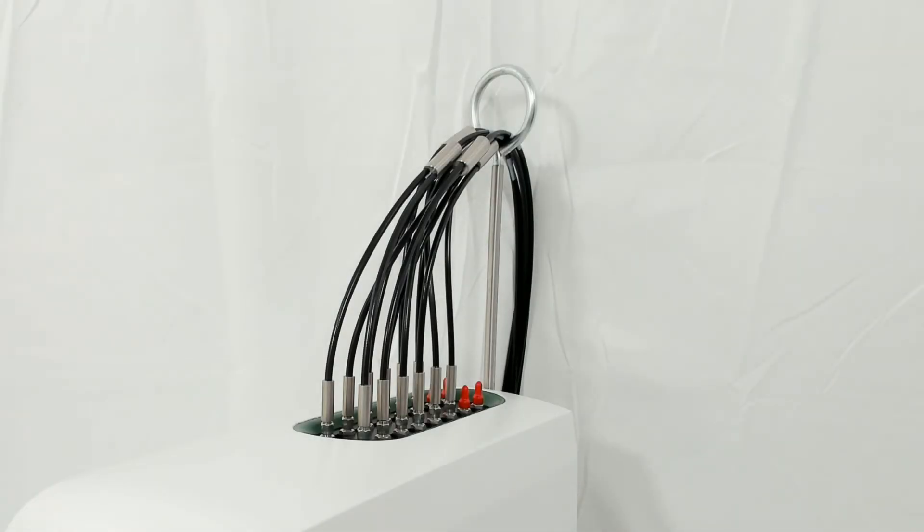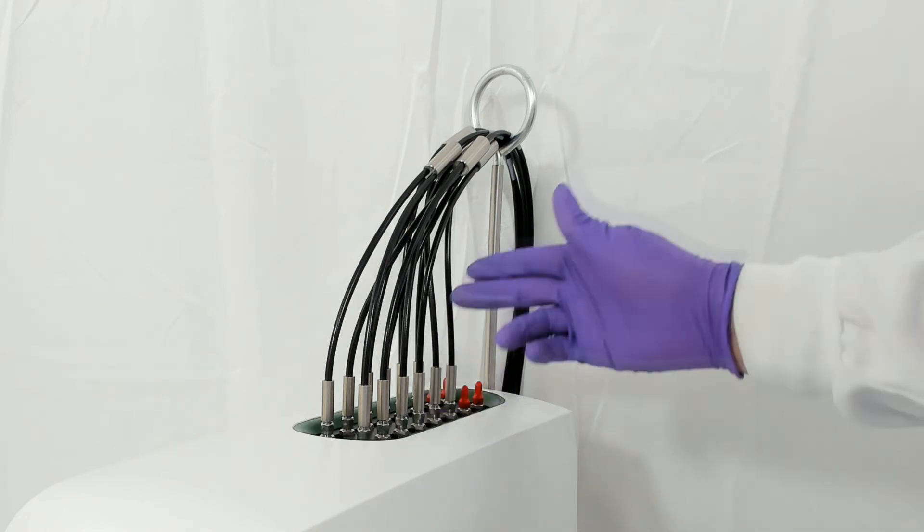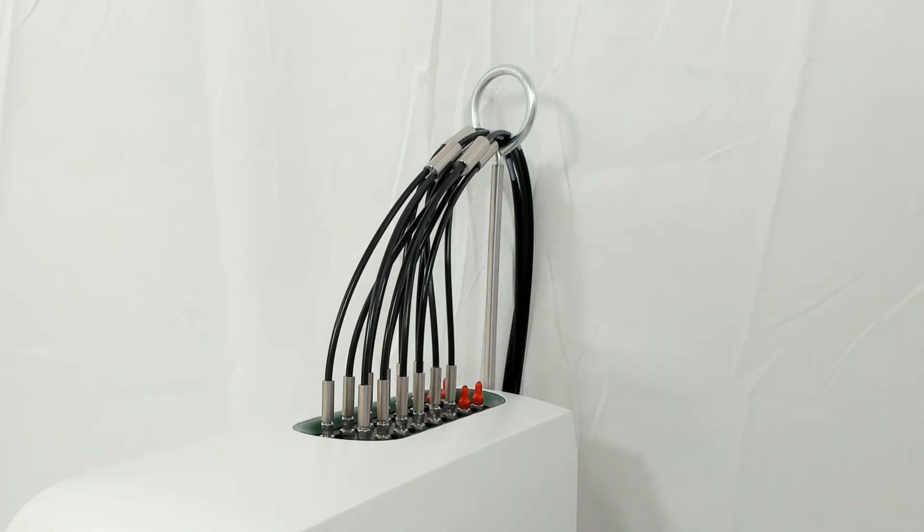Running from the top of the instrument, we have the fiber optic probes. There are 16 connectors on top of the instrument, facilitating the connection of up to eight probes on eight individual measurement channels.